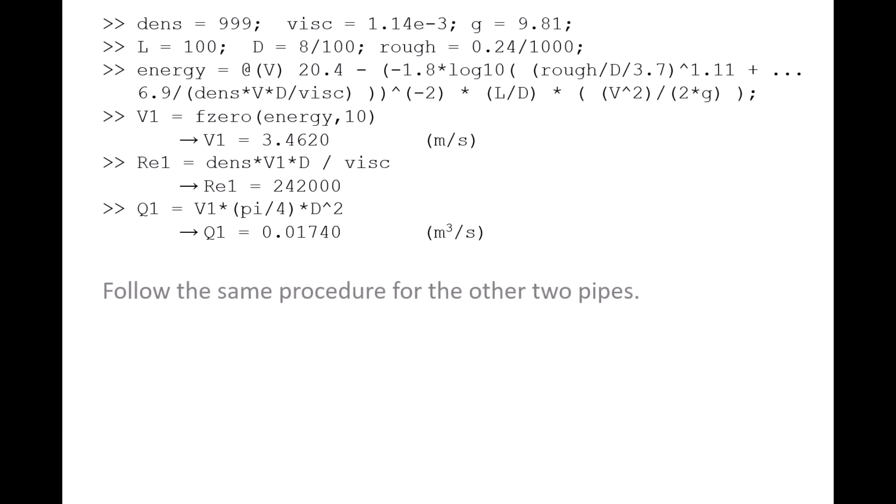If we repeat this procedure with the length, diameter, and absolute roughness of pipe 2 and pipe 3, we find that q2 is 0.007211 cubic meters per second, and q3 is 0.003173 cubic meters per second. Adding q1, q2, and q3, we find that the total volumetric flow rate is 0.0278 cubic meters per second.